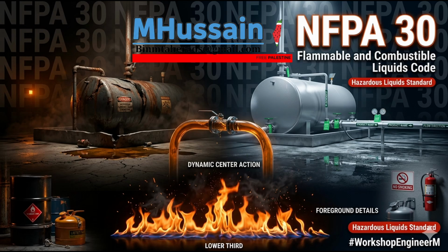And managing that vented energy requires strict oversight too. Chapter 27 governs piping and venting routing. If you have an emergency vent rapidly expelling highly volatile vapors to save the tank, where do those vapors go? The code is explicit. Vents must discharge vertically upward or horizontally away from adjacent structures. You cannot route vapor streams where they might pool under structural eaves.